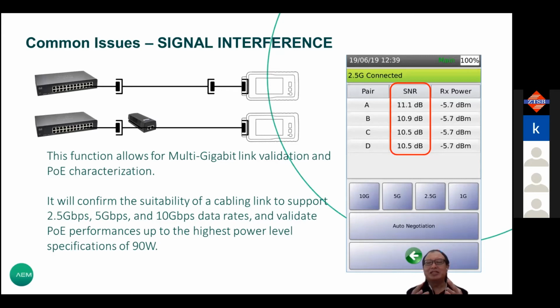So another issue is signal interference. Using the same tester, when the PoE is running and your data is running as well, what you see here is we are measuring real time, giving you a real time measurement when your data and power are running at the same time. And when we measure the signal, we measure a value called SNR, which means signal noise ratio. So signal refers to the 1 gig signal, 10 gig signal coming from the switch. Noise can be the noise coming from the power cable, or coming from external noise, any noise that interferes with your signal. So the signal and noise had to be at different levels.